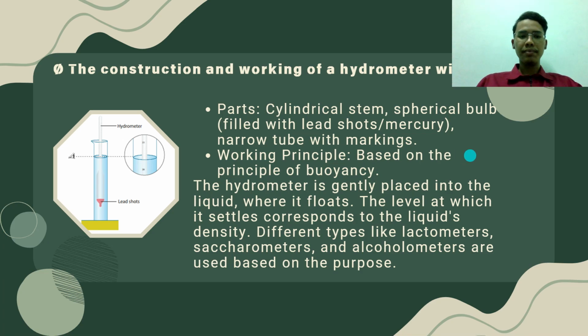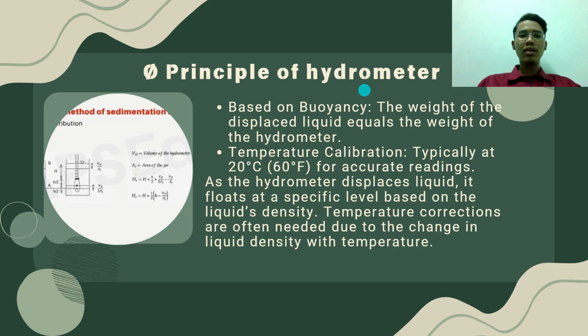Next slide is the principle of the hydrometer. Based on buoyancy, the weight of the displaced liquid equals the weight of the hydrometer. The temperature calibration is typically at 20 Celsius for accurate readings. As the hydrometer displaces liquid, it floats at a specific level based on the liquid density. Temperature corrections are often made due to the change in liquid density with temperature. So basically, we need to make sure the temperature is right so we can read the instrument correctly.